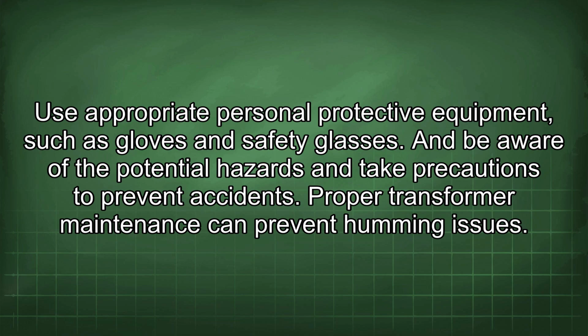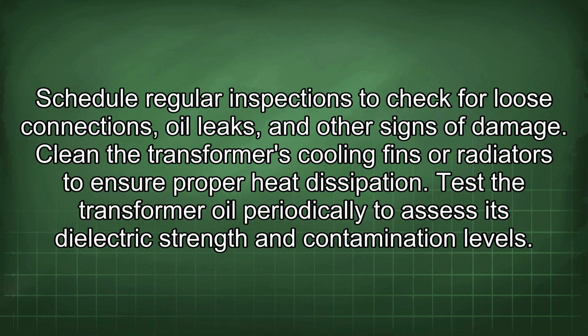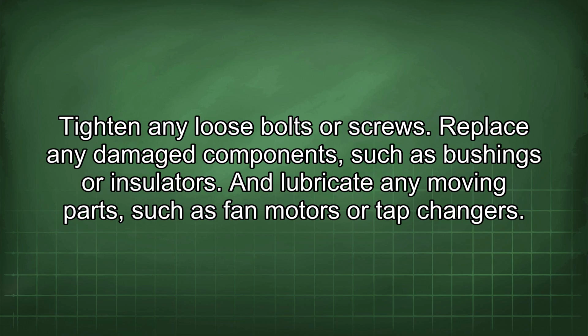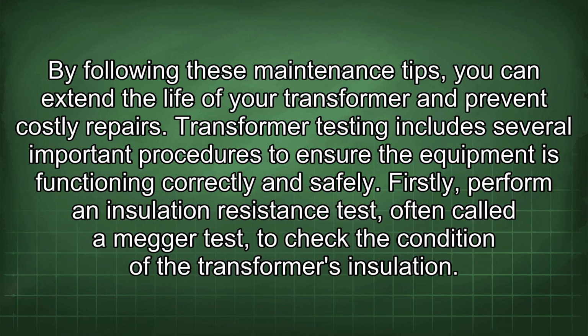Proper transformer maintenance can prevent humming issues. Schedule regular inspections to check for loose connections, oil leaks, and other signs of damage. Clean the transformer's cooling fins or radiators to ensure proper heat dissipation. Test the transformer oil periodically to assess its dielectric strength and contamination levels. Tighten any loose bolts or screws. Replace any damaged components, such as bushings or insulators. And lubricate any moving parts, such as fan motors or tap changers. By following these maintenance tips, you can extend the life of your transformer and prevent costly repairs.